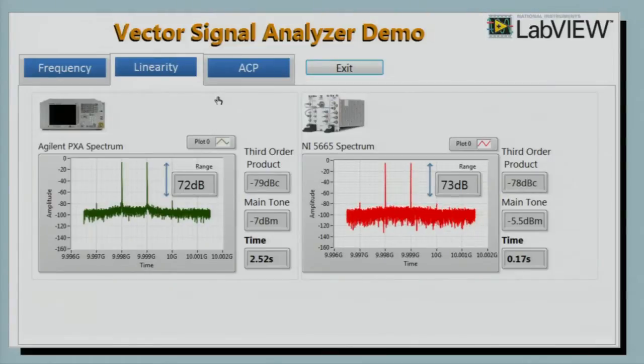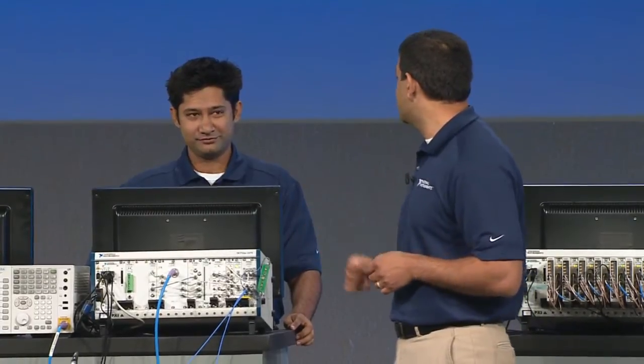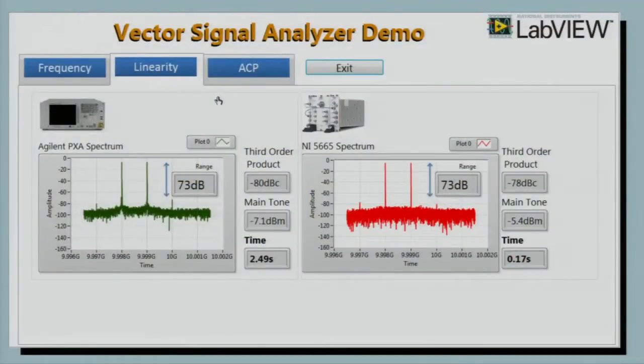Absolutely. For the first test, we're generating two tones spaced 1 MHz apart with center frequencies close to 10 GHz. These are synthesizer modules from Phase Matrix using their QuickSyn technology — products that go up as high as 20 GHz with very good phase noise performance, generating really clean tones, which is exactly what we wanted for this demo. What you're seeing on the screen are the two spectrums acquired by the Agilent PXA and the NI-5665. You will notice that both instruments have world-class dynamic range and are measuring about 73 dB at 10 GHz.